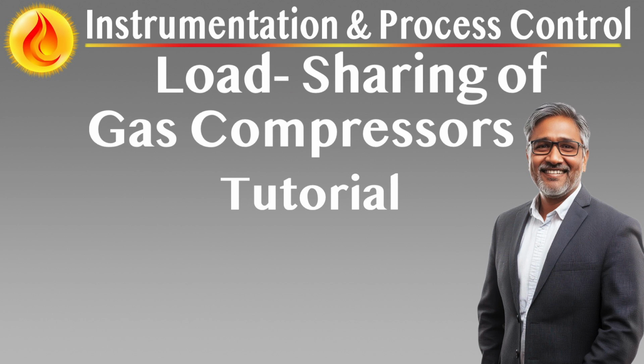Recycle rate equalization, activated when multiple compressors are simultaneously in recycle, ensures that no single compressor remains disproportionately in a recycle state. When surging is receding, the most open valve is closed faster, while others slow their closure. When surging is imminent, the most critical valve remains open and others accelerate to match its flow. Enhances equipment protection and reduces cyclic wear.